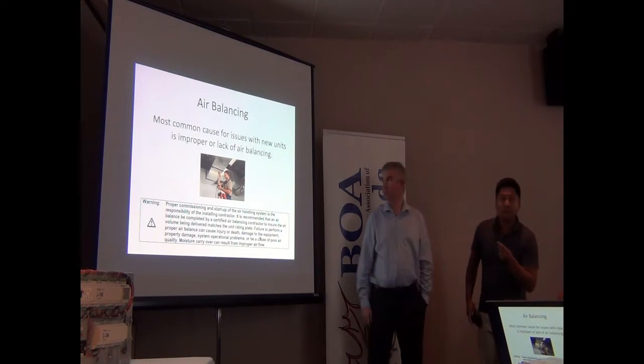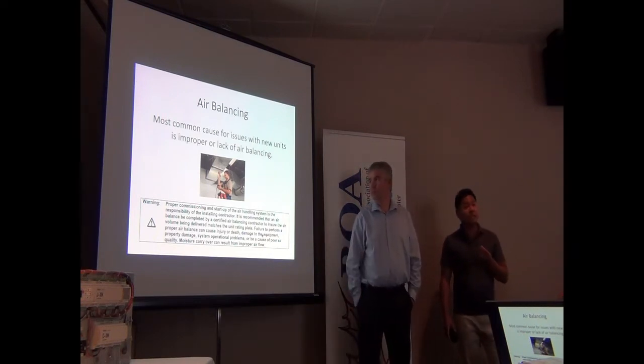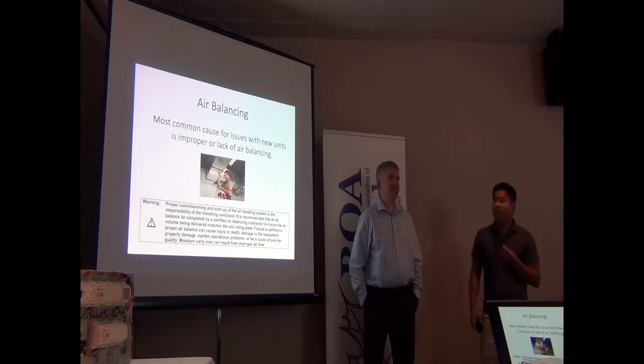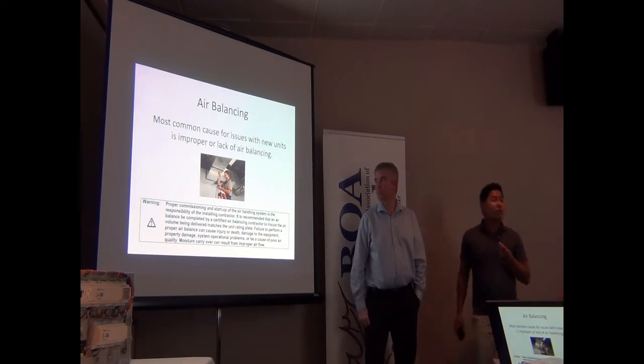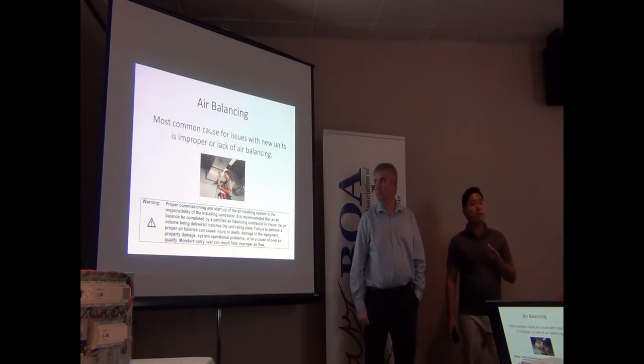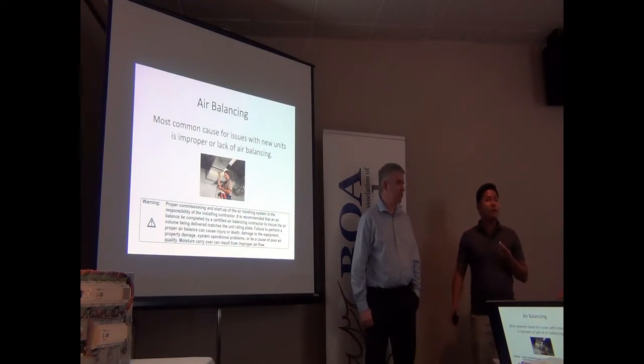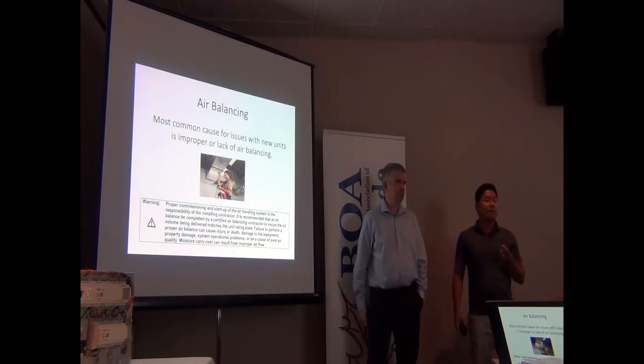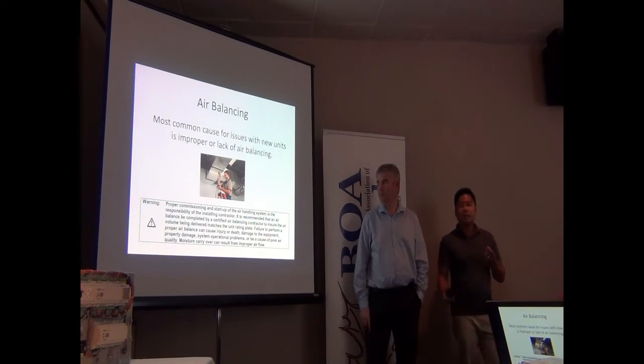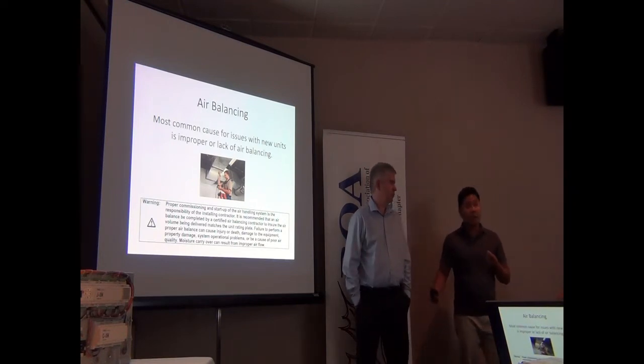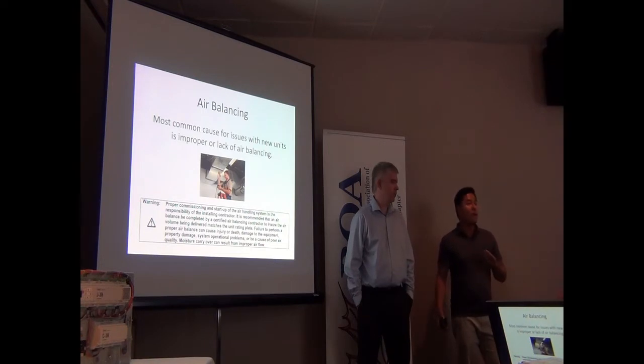So like you said, sometimes oversizing is not a good thing. We recommend all new equipment gets air balanced. I'd say the most common issue we find with new equipment is improper air balancing or lack of air balancing. Oftentimes the external static pressure will be overestimated, and what's actually on site you have much less. Most of the time, our units are over delivering.